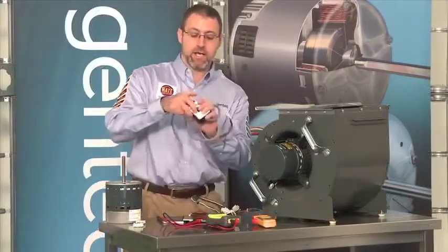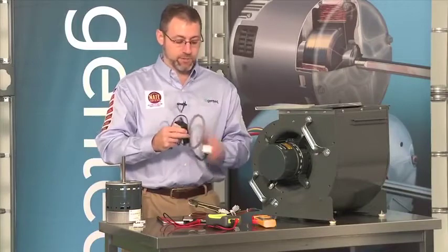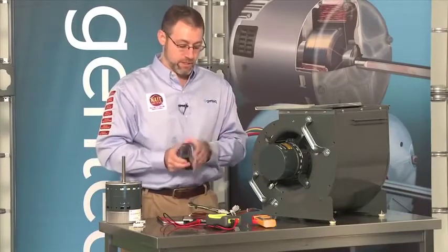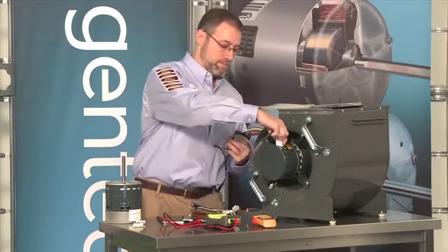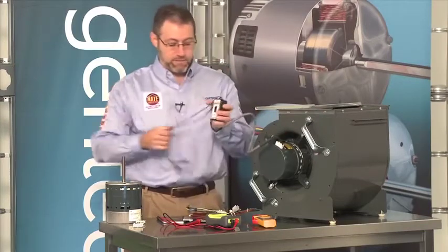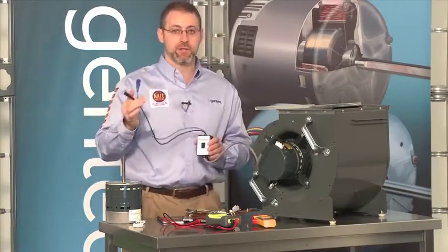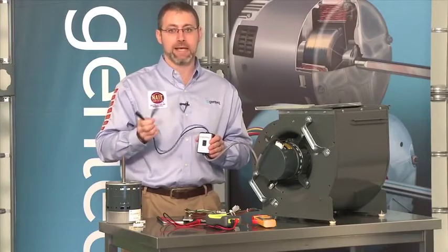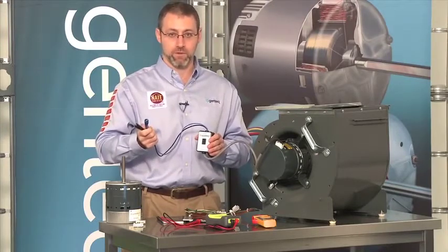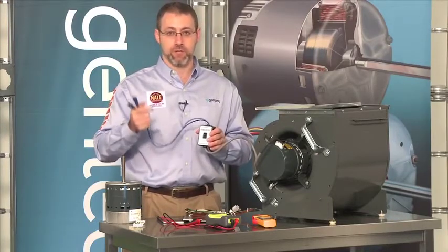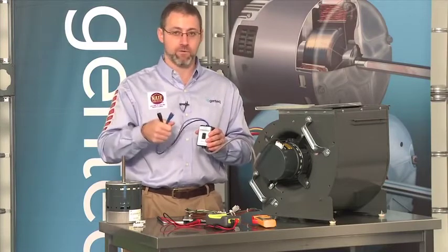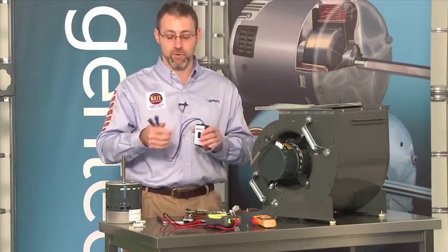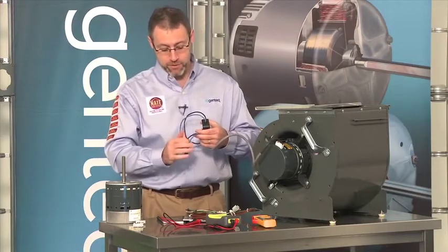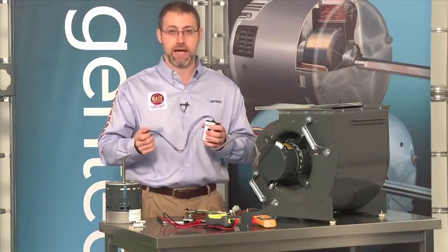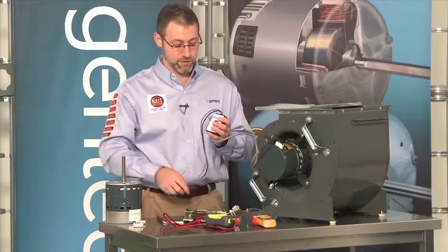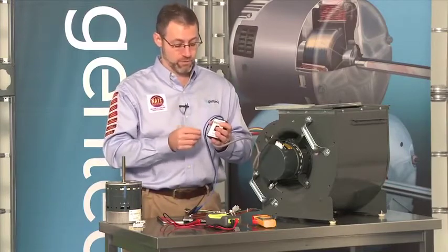So, on our TecMate, we have 2 connections. We have a 16-pin connector that we will plug into the motor, and we have 2 wires. These 2 wires are what will power the TecMate, and we will connect this to 24 volts. And that can be 24 volts at your thermostat connections or 24 volts directly at the transformer. And I should also say that even though they're 2 different colors, they are not polarity sensitive. You can connect them to either side, common or 24 volt.